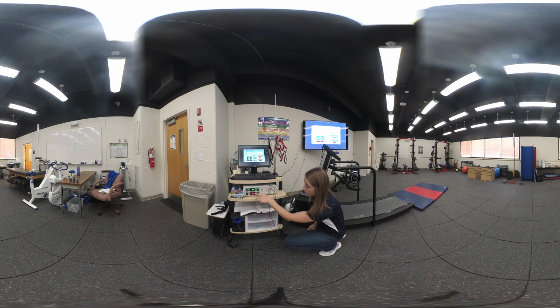What you're noticing on the front of the screen is actually adjusting to the correct calibrations for the gas. So I'm right on the dot at 16 for O2 span, and I'm getting pretty close here to 4 for the CO2. So you can see my calibration is slightly off, and this is what's going to correct that calibration, because we're going to tell the computer this is what 4 should be based on what's in the gas tank. And so my little dot is right in the green area, so I'm going to go ahead and hit start. So it gave me a thumbs up smiley face again that that part was complete.